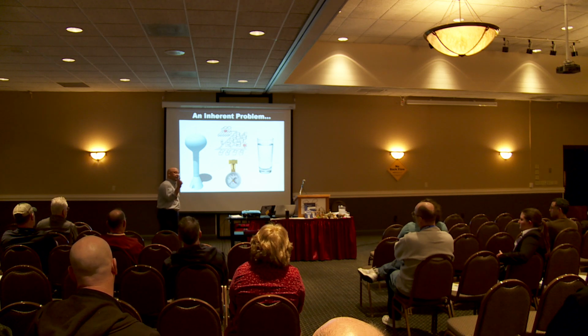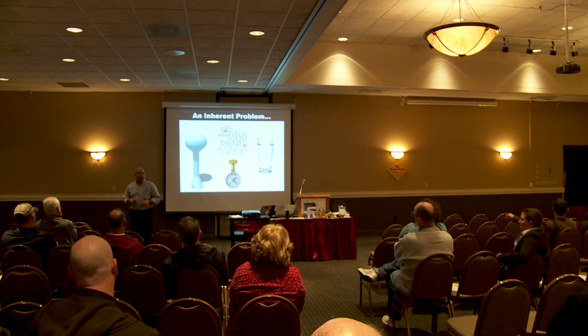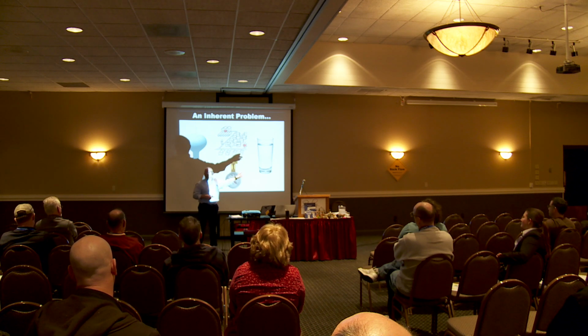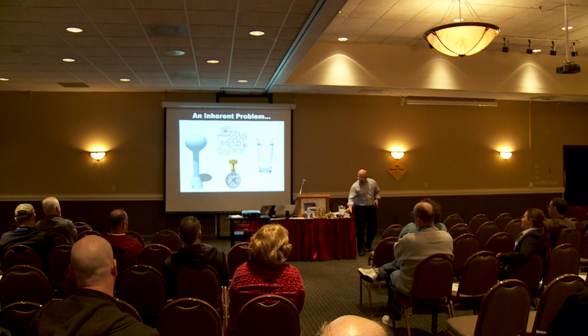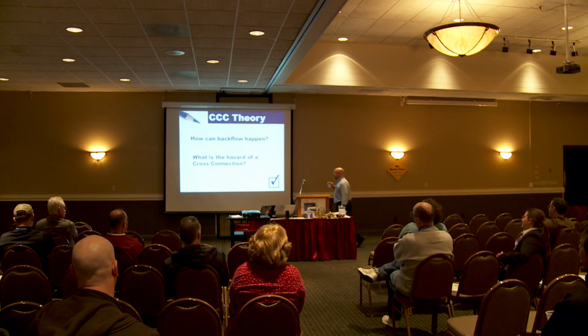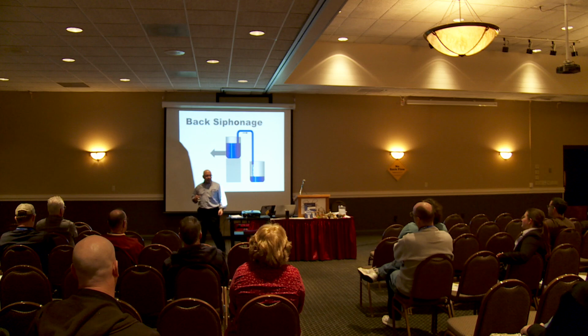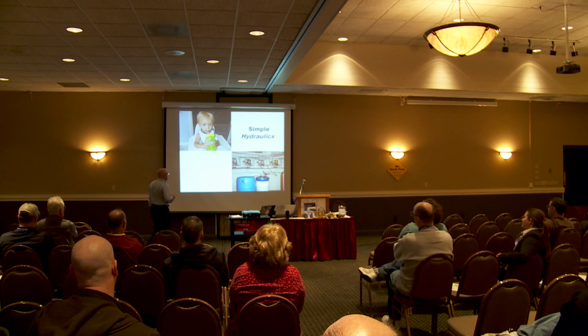We know we have main breaks. We know we do have to do flushing and other things where we're going to have that sudden change in pressure. This is why I say inherent problem. Regardless of regulatory issues and things like that, we're dealing with a hydraulic issue when that pressure drops. And our drinking water supply is on the other end of it. Oh, and by the way, what else is connected to our plumbing system that we get drinkable water from? We have other pipes connected to boilers, and that end supply is supposed to be potable, right? So we have back siphonage. Pretty simple, right? Pretty simple hydraulics.